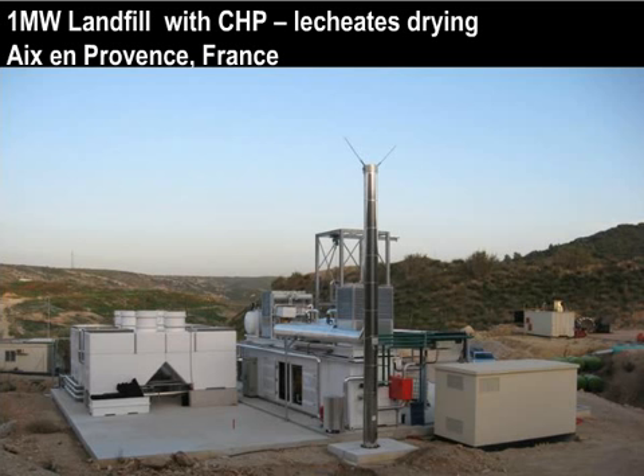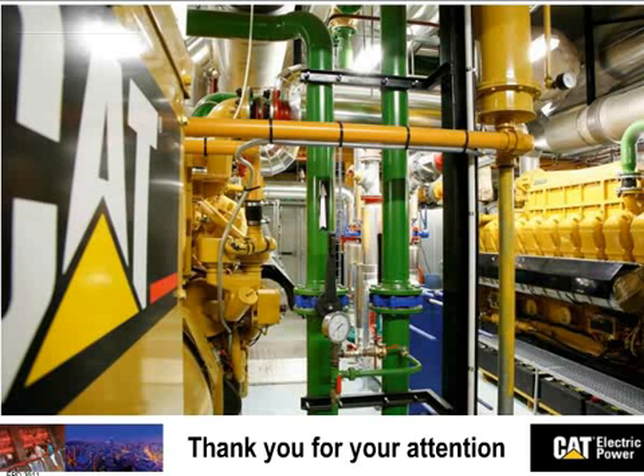Thanks, Francois. Good question coming in from Kip Doyle at ITG. He notes that in your exhaust application, you seem to go below condensation temperatures. How do you handle condensation in the exhaust system? Condensation in the exhaust system is becoming more and more popular, and what we want to capture here is the famous high heat value I discussed earlier. This is 10% of the energy in your gas that you can capture if you condense. So that's something we don't want to let go.